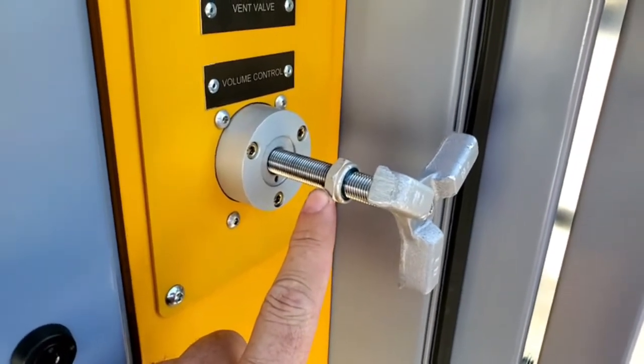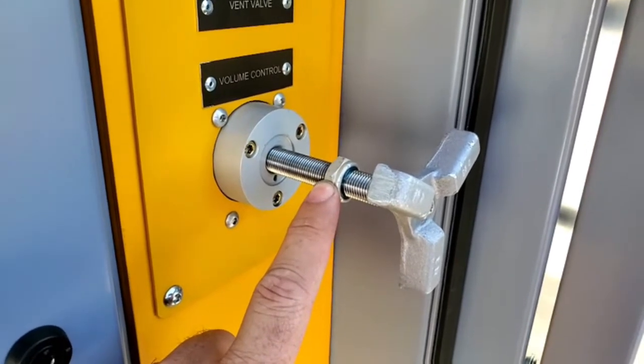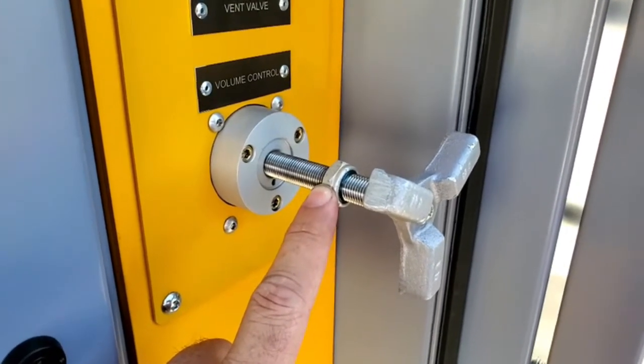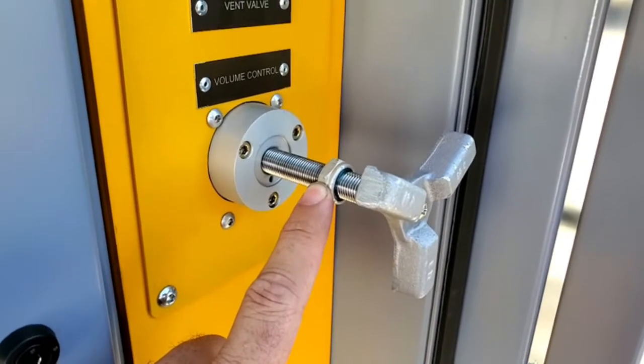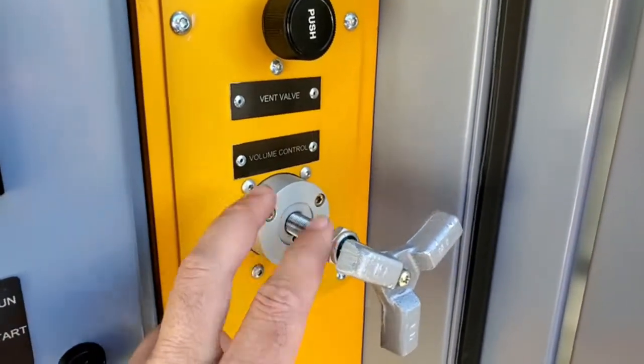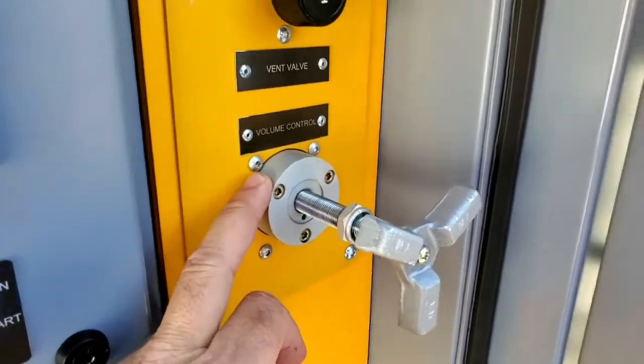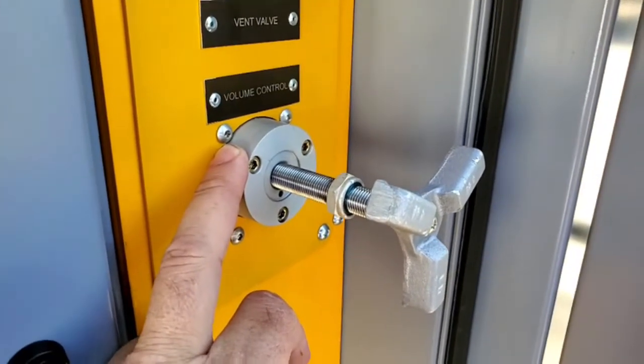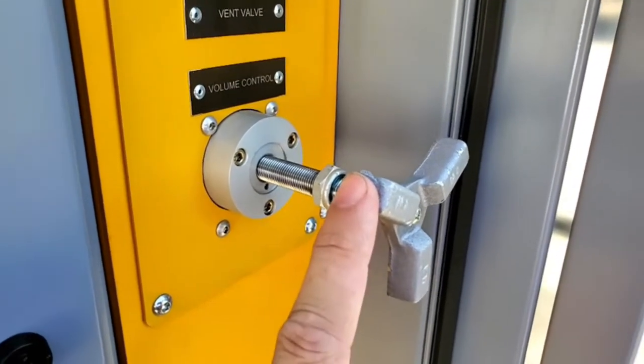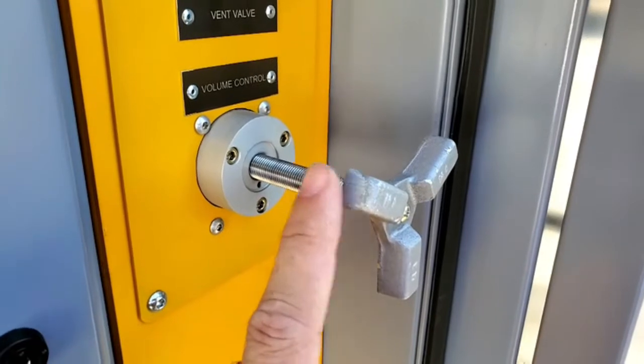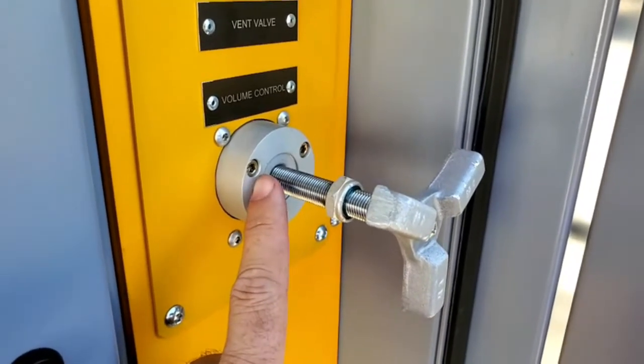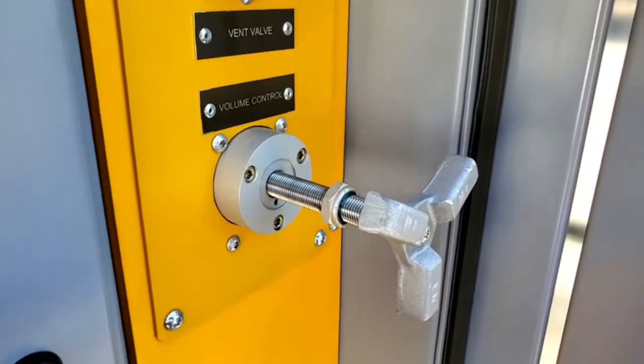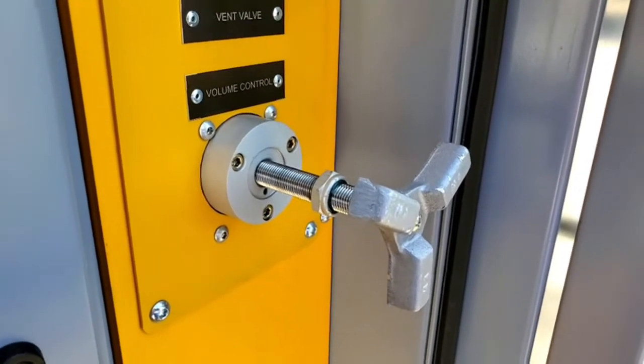This nut is important. It should remain in place. It should never be adjusted. If you have to adjust this, then you need to more than likely recharge your volume control system, which I'll cover later. So as you rotate this fully clockwise and you bring this nut to stop, your gallons per minute should be around 3 to 5 gallons per minute.